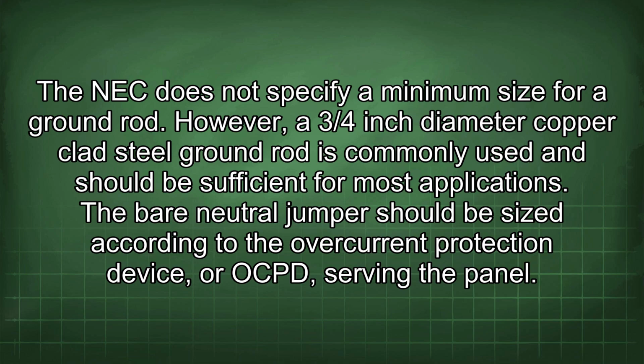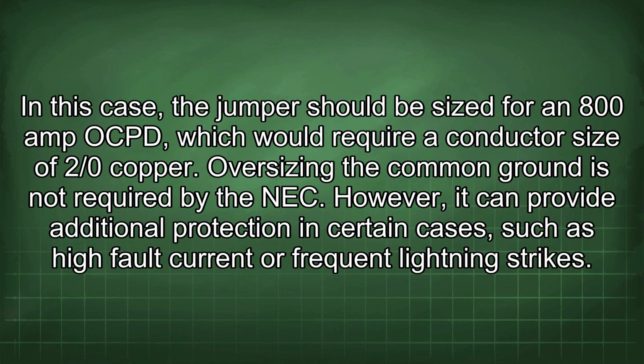The NEC does not specify a minimum size for a ground rod. However, a 3/4 inch diameter copper-clad steel ground rod is commonly used and should be sufficient for most applications. The bare neutral jumper should be sized according to the overcurrent protection device, or OCPD, serving the panel. In this case, the jumper should be sized for an 800 amp OCPD, which would require a conductor size of 2/0 copper. Oversizing the common ground is not required by the NEC.